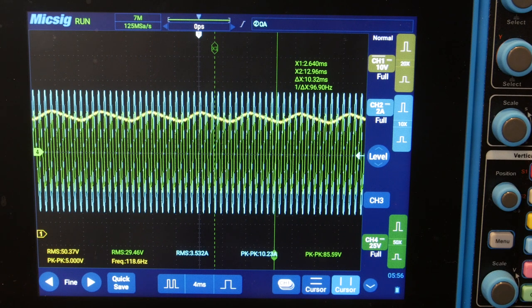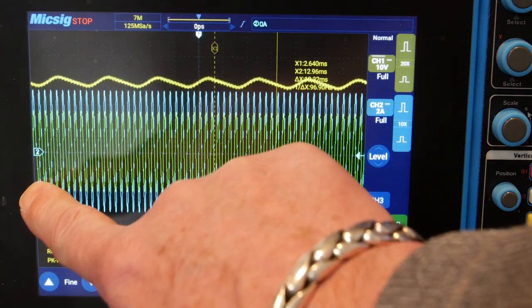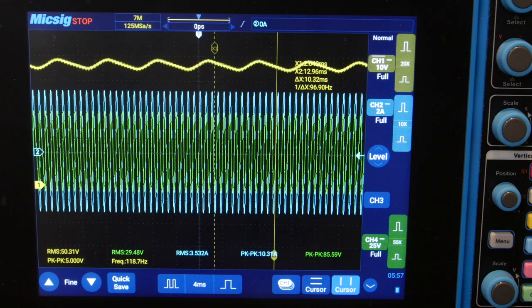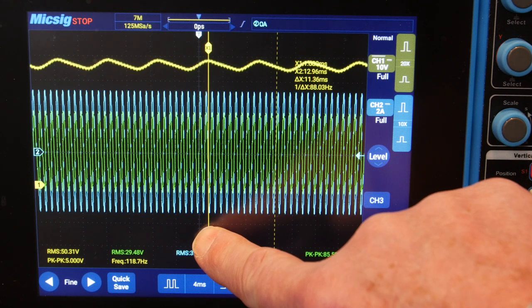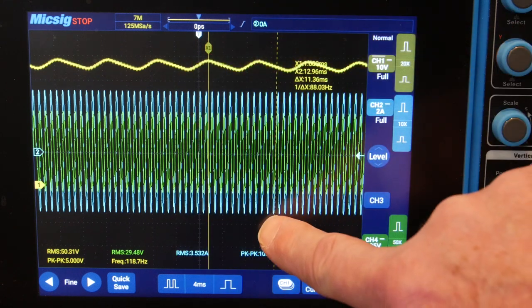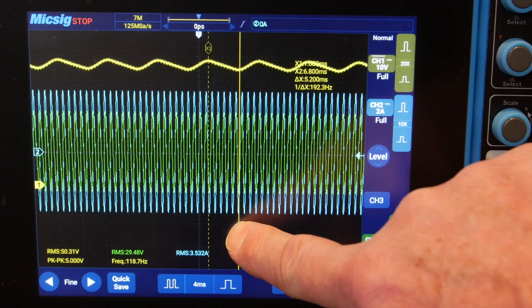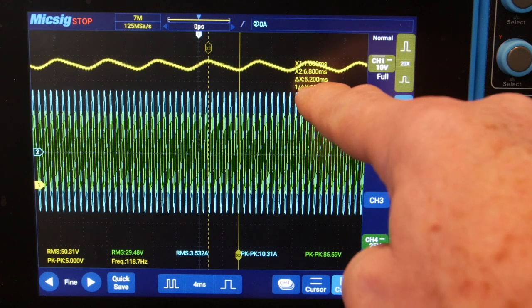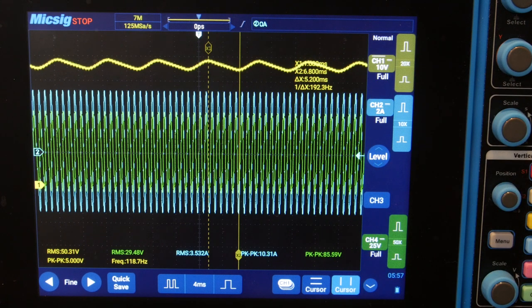Here, I'm just going to go ahead and freeze that. And I'll bring this voltage up a little bit. So you can see the waveform. Okay, then I'll bring this cursor. One cursor right there. See how it charges right up from this valley to that peak? And let's just drop that to the valley. And that's where it discharges in that time. Yeah, that's pretty close. And so that's about 5.2 milliseconds discharging. And, you know, that's about what we'd expect.